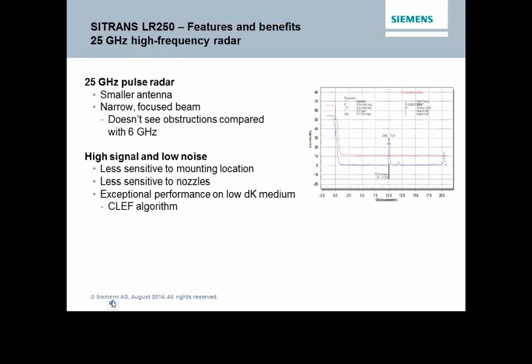The CLEF algorithm is constrained leading edge fit. If I have a tank with a liquid in it and I get near the bottom of the tank, I can maintain my material surface level instead of getting the bottom of the tank. Because the radar is actually measuring the bounce back, when I get near the bottom of the tank, I can get to where the signal off the bottom of the tank is actually stronger than the material signal, and I can adjust for that.